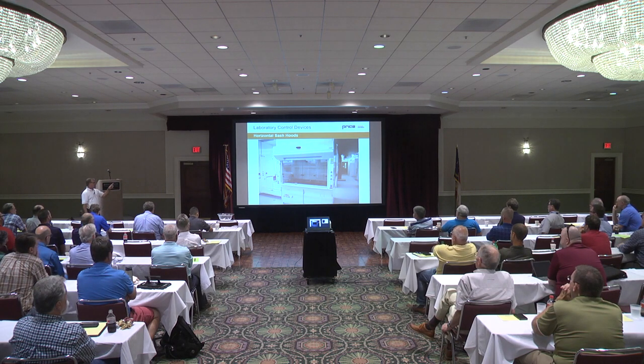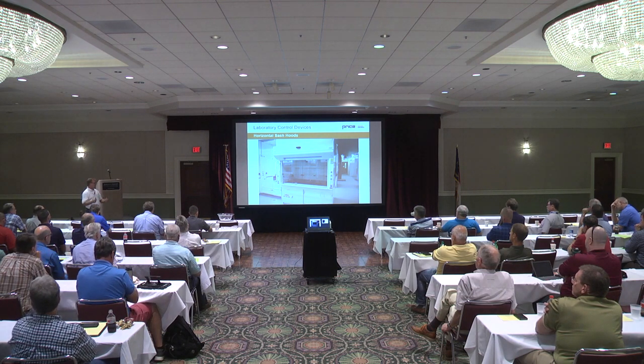Here's an example of a combination fume hood, with vertical and horizontal sashes. Just another challenging VAV hood, because you have to be able to control the airflow with the vertical and the horizontal at the same time, meaning partial horizontal open and partial vertical open, independently, whatever's necessary for that fume hood use by the occupant.